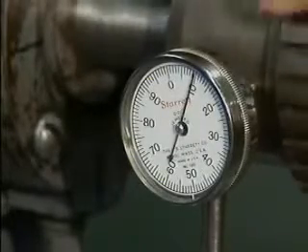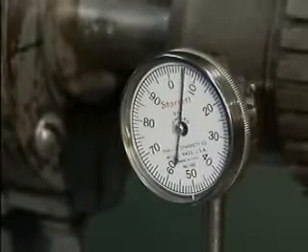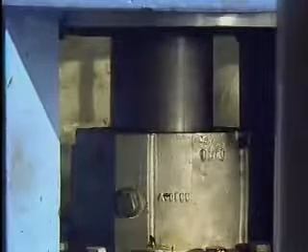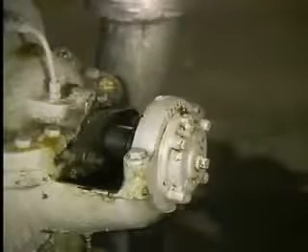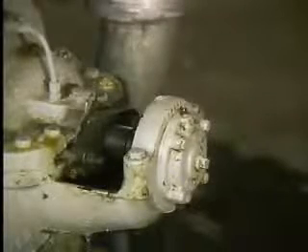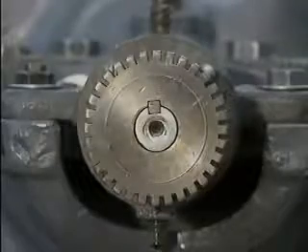A shaft typically has some run-out or eccentricity during its rotation. However, too much run-out is an indication of a problem. For example, a bent shaft or worn or damaged bearings could cause eccentric rotation of the shaft. A defective coupling that's out of round could also cause an excessive run-out reading.